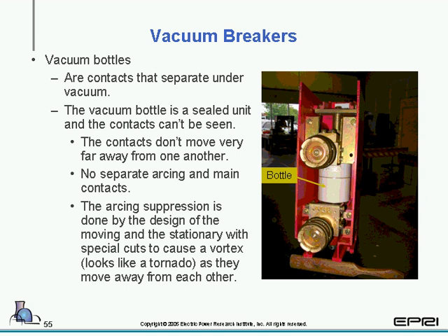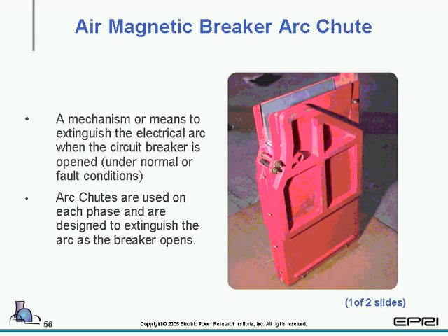Now, the vacuum bottles are contacts that separate under a vacuum. The vacuum bottles are sealed units. They don't move very far away from one another, and there are no separate arcing and main contacts. They're actual discs, or look like little plates, that come up and touch one another. Arc suppression is done by the design of the moving from the stationary, with special cutouts in them that cause a vortex or tornado, if you will, inside of the vacuum bottle. That's what helps produce the arc quenching ability along with the vacuum.